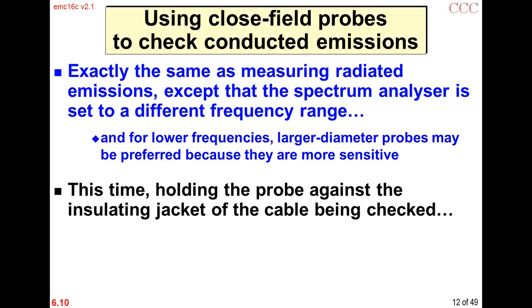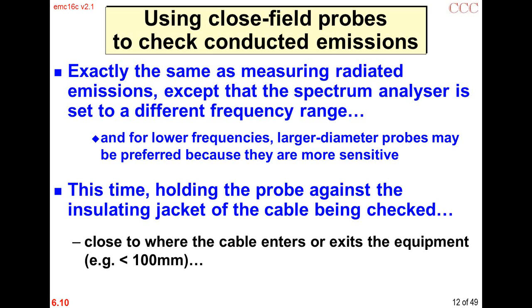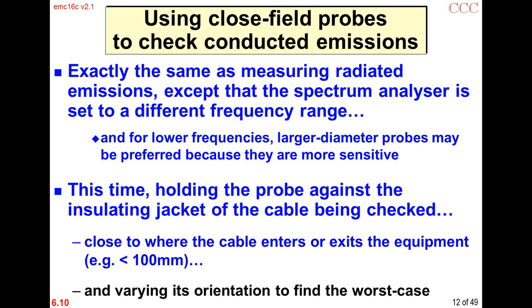When we're measuring conducted emissions, we hold the probe against the jacket, the insulation of the cable we're checking, close to where it enters or exits the equipment, say less than 4 inches away, and find the worst case. Now, if your filters and shielding are working properly, then you shouldn't see any untoward noise on the cable at that point.